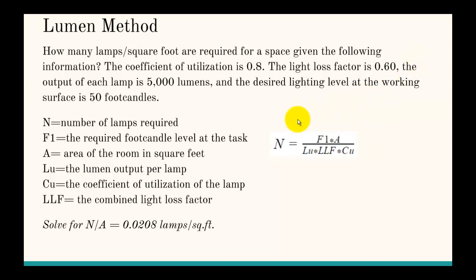To the right here is the general formula for the lumen method and all the different variables. In this case we're solving for how many lamps per square foot. Since A is the area in square feet, we divide both sides by A and get N/A equals F1 over LU times LLF times CU. Plugging in all the values, we get 0.0208 lamps per square foot.